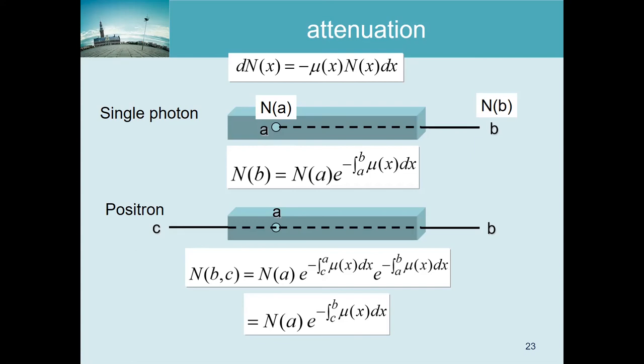For PET, a coincidence is only detected if both photons arrive, since we check whether two photons arrive at the same time. With a point source emitting one photon toward detector B and one toward detector C, we compute the probability that each photon reaches its detector - exactly the same formula as before, with mu reflecting each photon's energy. The total coincidences detected is proportional to the number of photon pairs, times the probability the first photon arrives, times the probability the second arrives - assuming the two events are independent.